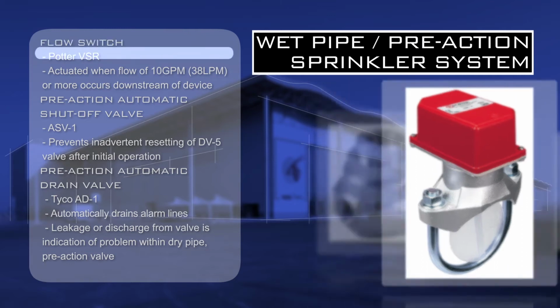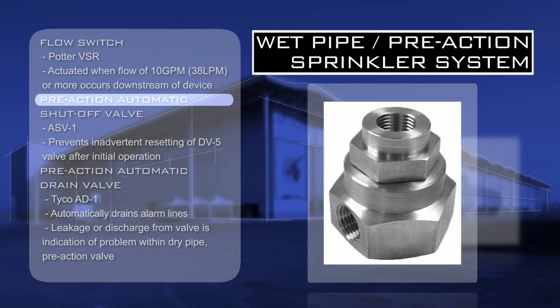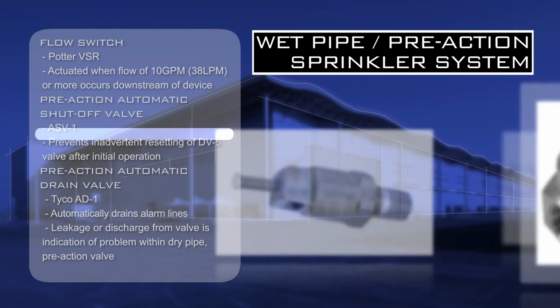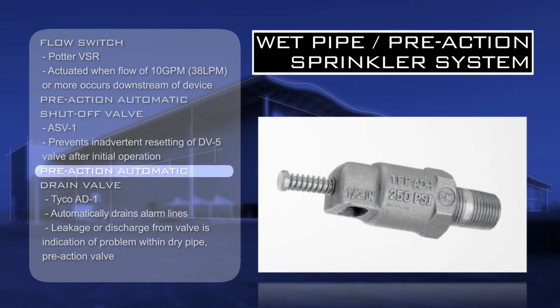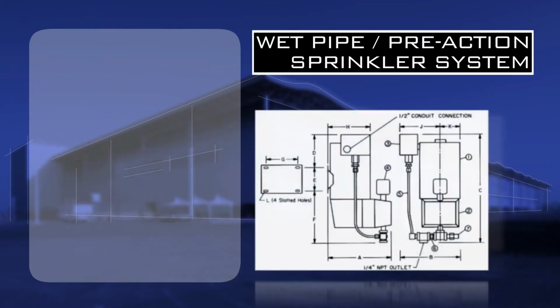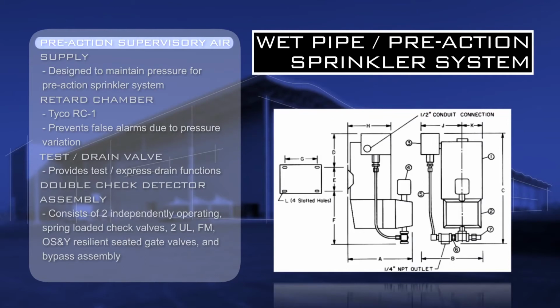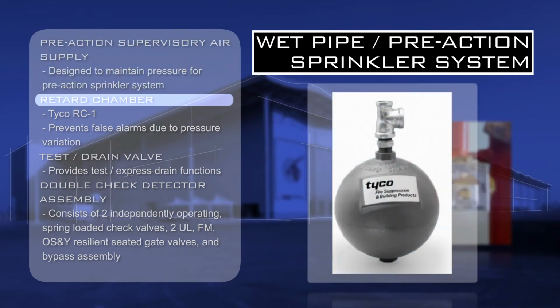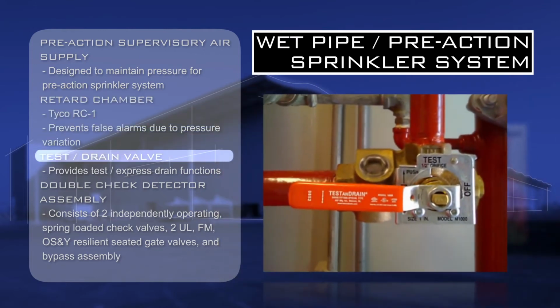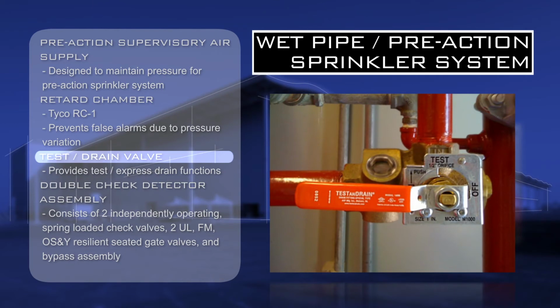The pre-action shut-off valve prevents inadvertent resetting of the DV5 valve after initial operation. The pre-action automatic drain valve automatically drains alarm lines. Any leakage or discharge from the valve is an indication of a problem within the dry pipe or pre-action valve. The pre-action supervisory air supply is designed to maintain pressure for the pre-action sprinkler system. The retard chamber prevents false alarms due to pressure variations. The test and drain valve provides test and express drain functions.